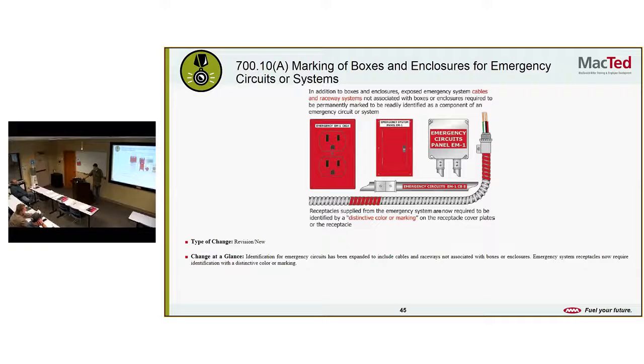Marking of boxes and enclosures for emergency circuits and systems. Identification for emergency circuits has been expanded to include cables, raceways not associated with boxes or enclosures. Emergency system receptacles now require identification with a distinctive color or marking. Seems like that's been around for a while, marking things red or with labels, it's part of an emergency circuit. But now they're including cables and raceways that are not associated with boxes or enclosures. So they just kind of want everything red that has to do with an emergency circuit.